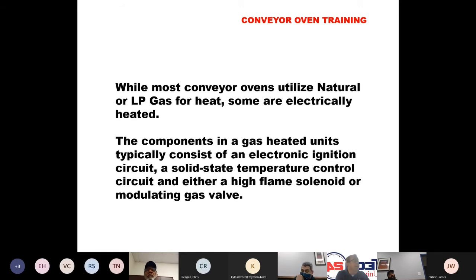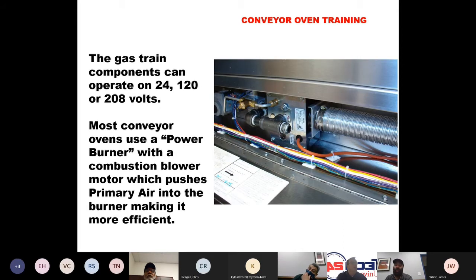The components in gas-heated units typically consist of an electronic ignition circuit, a solid-state temperature control circuit of some type, and then either a high-flame solenoid or a modulating gas valve. This is the gas train on a 500 series Middleby oven. These gas trains may operate on 24 volts, 120 volts, or 208 volts.